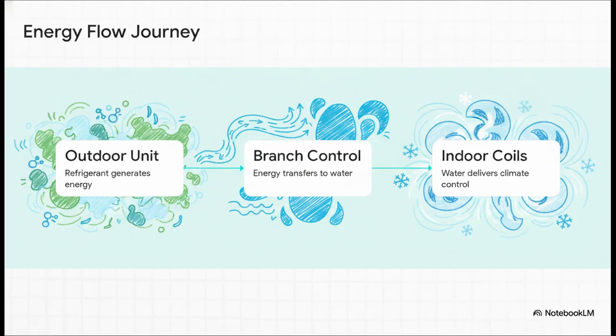If we follow the energy, it's a super clean, logical flow, like a perfectly choreographed relay race. You start at the outdoor unit, where the refrigerant generates the energy. Then you pass the baton in the mechanical room at the hybrid branch controller, where that energy safely transfers to water. Finally, you reach the indoor fan coils, where the water actually delivers the climate control into the room. It totally isolates the complex chemicals right to the mechanical zones.